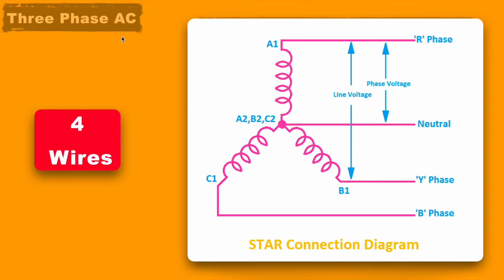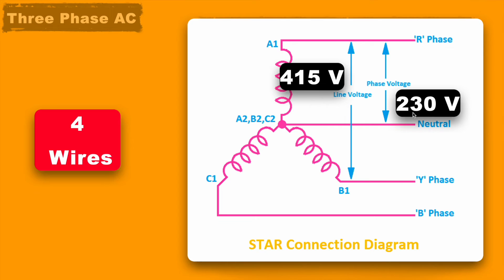Mainly 3 phase power supply has 2 configurations. The first one is called a star connection as you can see in this diagram. Here it has 3 phases: R phase, Y phase and B phase, and one common line neutral. The phase to phase voltage, which is called line voltage, is approximately 415V and the phase voltage with respect to the neutral is approximately 230V.